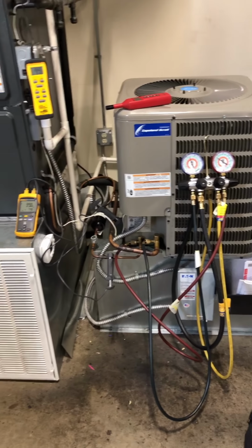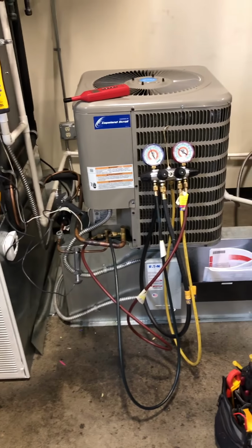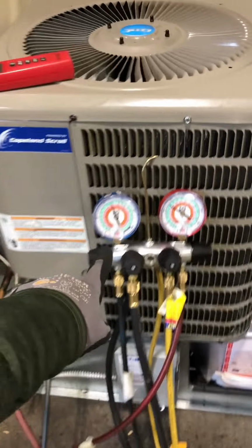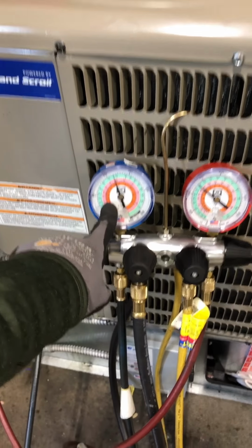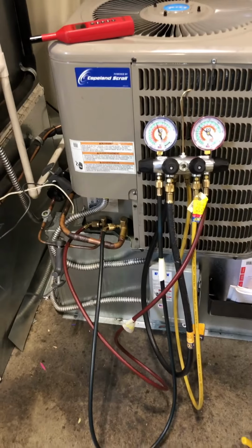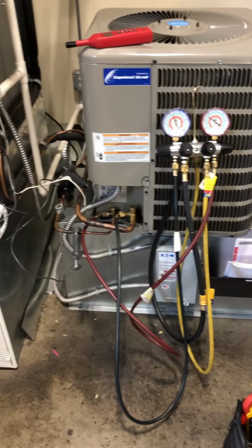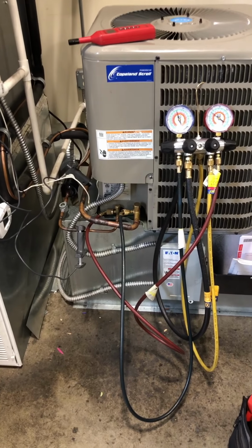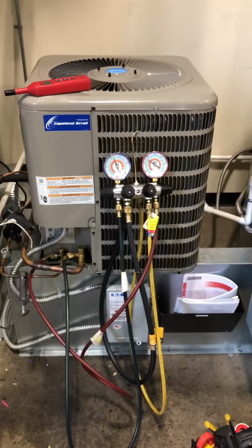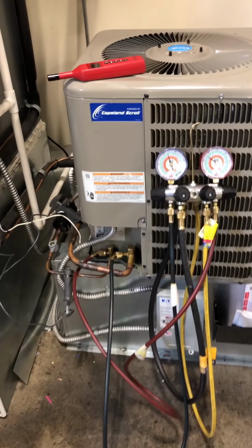You can't just go inside and take an air temperature split and determine that it's low on refrigerant. You can't just go outside and plug your gauges in and look at the suction side, and based on what you see on the suction pressure, determine that you have an airflow problem. You can't make that type of decision off of one thing. So you've got to look at all your KPIs, your key performance indicators. Okay, it doesn't take very long. You're taking in all the information, and based on the information you get, you can make a better determination of what's going on.